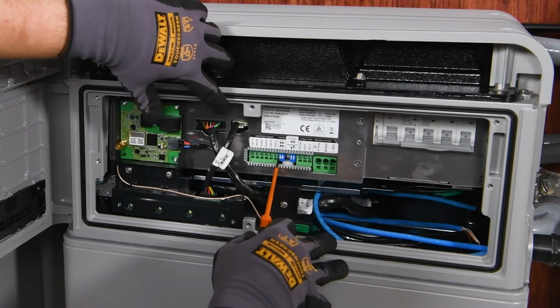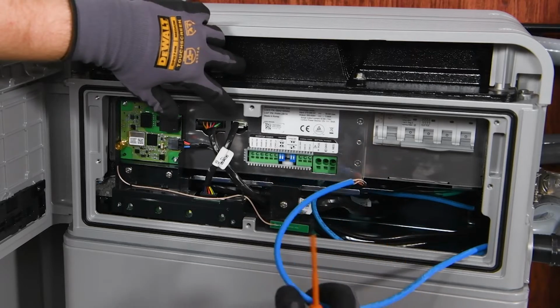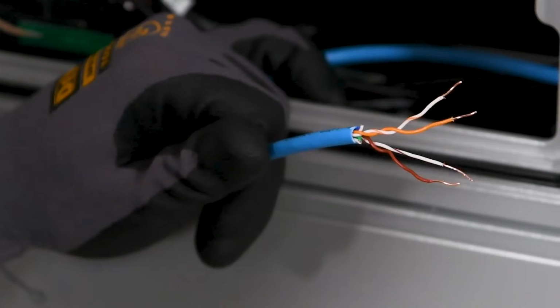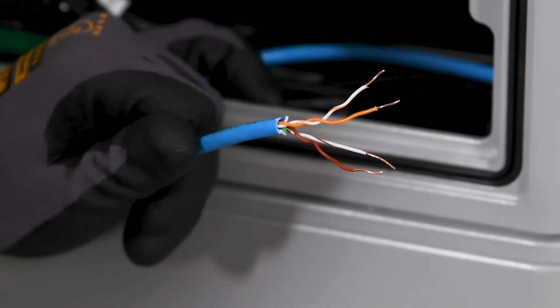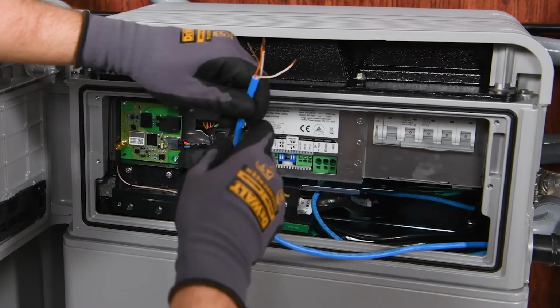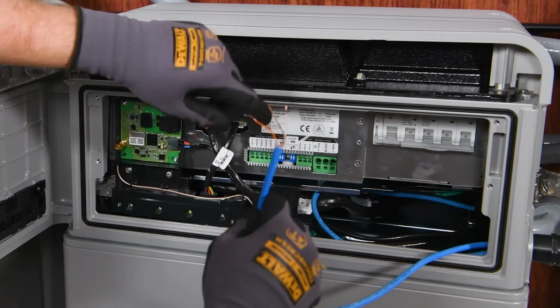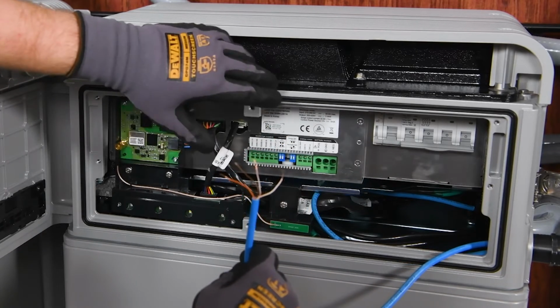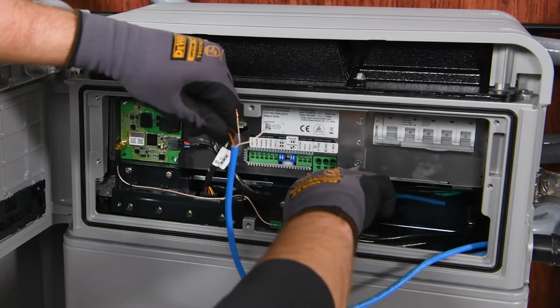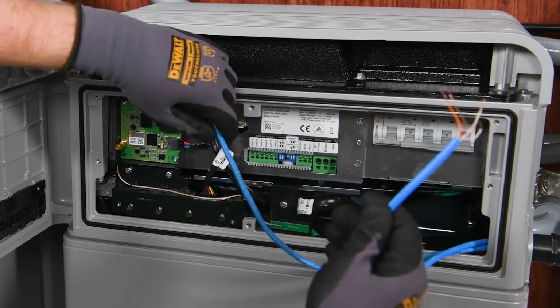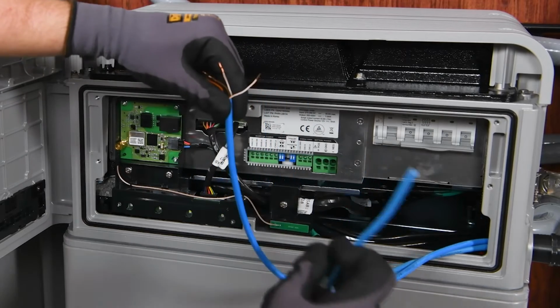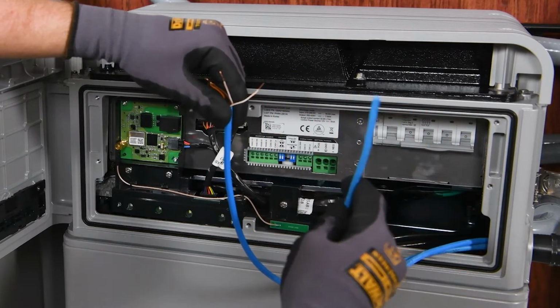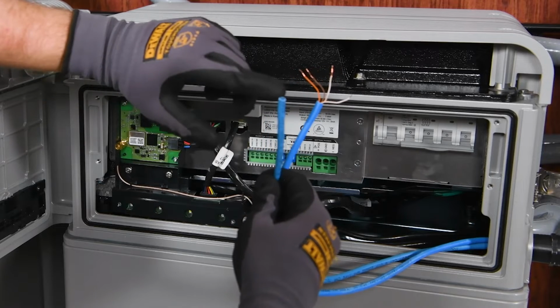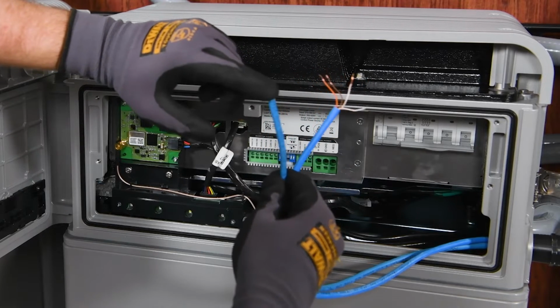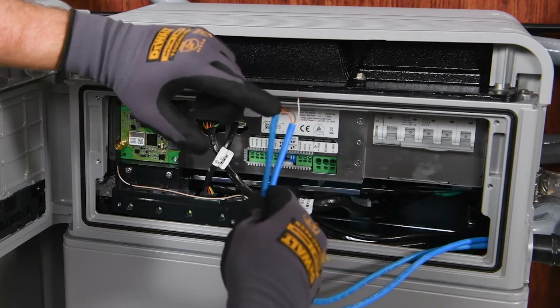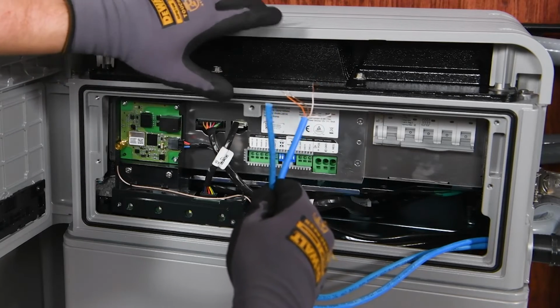Again, we'll adjust the dip switches, but for now, we'll want to set up the communication cables as we did with the primary battery. We'll use orange, orange-white, brown, and brown-white as our 4 conductors. Again, we'll set them up the exact same way using the same inverter comms ports as we did with the primary battery. The only difference is we are routing our primary battery cable that we just wired to the secondary battery. And we are taking our secondary battery communication cable, and this cable right here will run and set up communications between the Growatt 11.4 inverter and the LG Prime battery stack that we just created.